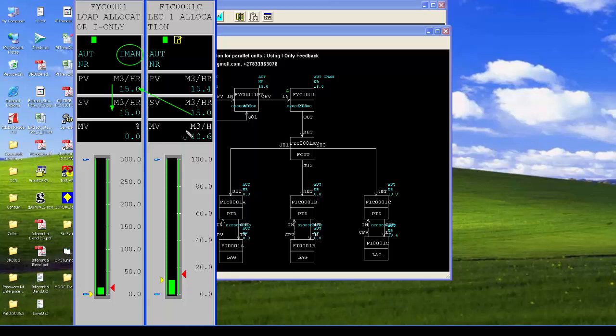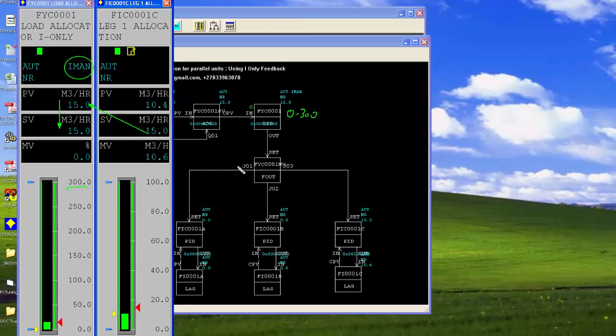With set point PV tracking now enabled, taking the set point of the slave loop to 15 immediately shows these two values are tracked. The master FYC loop is ranged from 0 to 300, while each of the slave loops is ranged 0 to 100 — so 3 times 100 equals 300, which makes sense. Each slave loop is in cubic meters per hour.